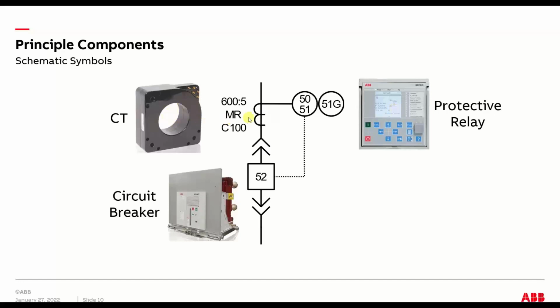CT, here's the actual CT. The ratio, this one was 600 to 5. The 5 on the secondary was historically the default standard secondary CT current in North America. So every CT was something to 5 in North America. Now, if you go into the European market, they had a lot more of the X to 1 ratio. So they used 1 as a secondary current versus 5 in North America.